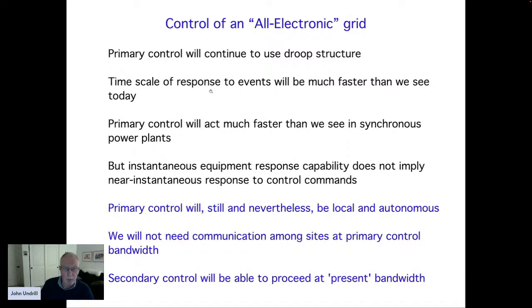Primary controls will have to be tuned to be quick responding. And the response of the equipment that we see will be correspondingly fast, but not necessarily as fast as you might believe, considering that an inverter can probably maneuver the amplitude of a voltage in a half a cycle. You're not going to see equipments responding in a half a cycle. You're going to see equipments responding in tens or hundreds of milliseconds. The primary control will still be local and autonomous. We don't have to be dependent or become dependent on broadband bandwidth control.